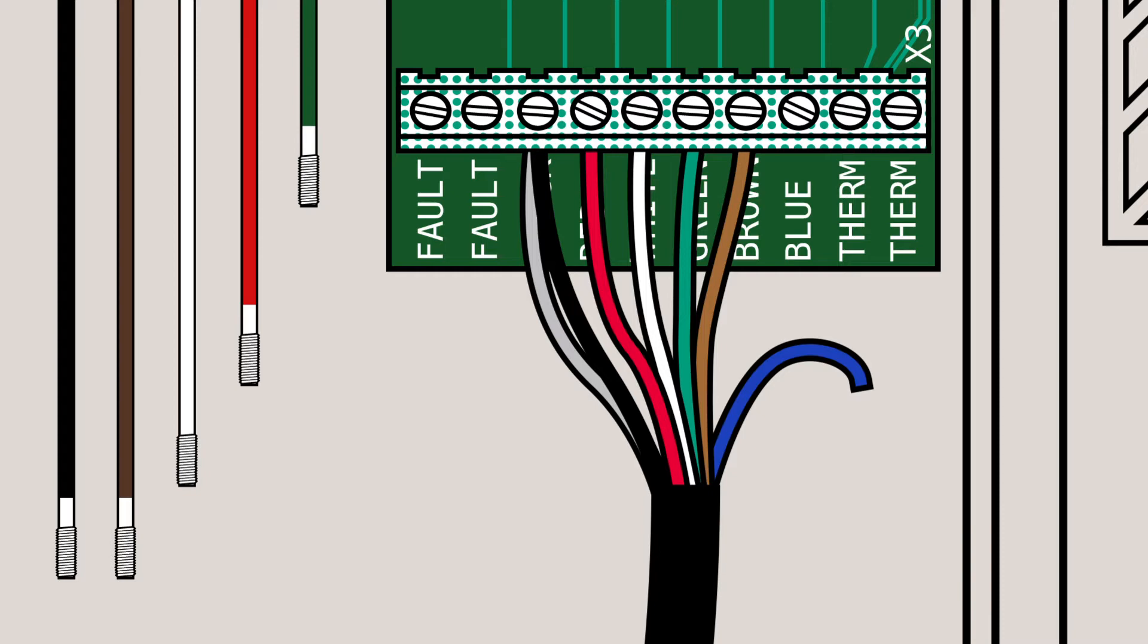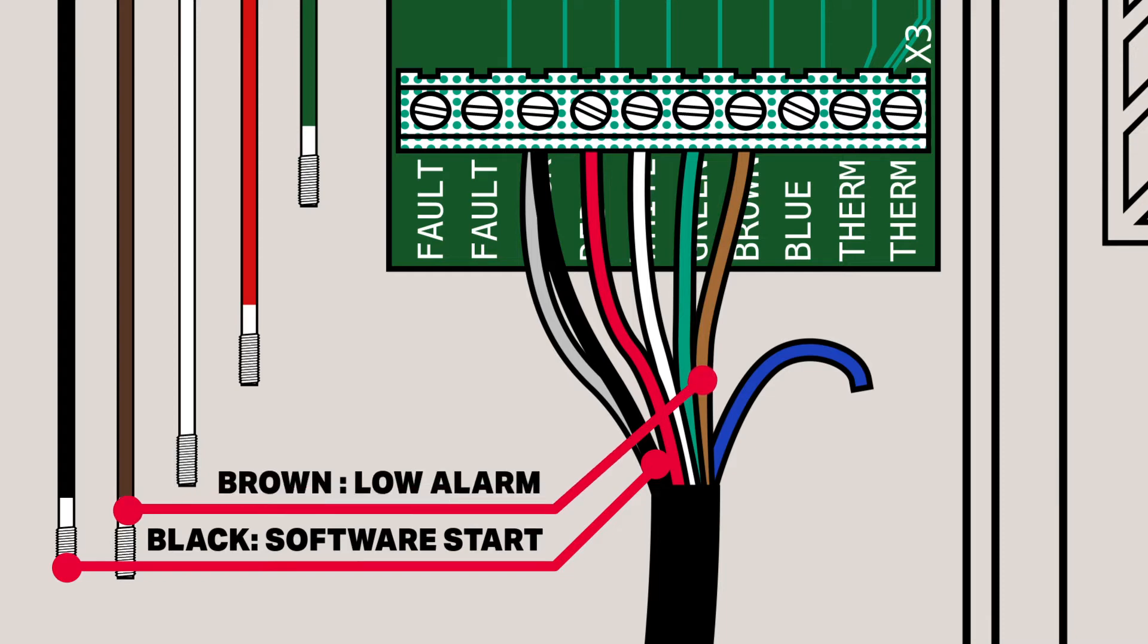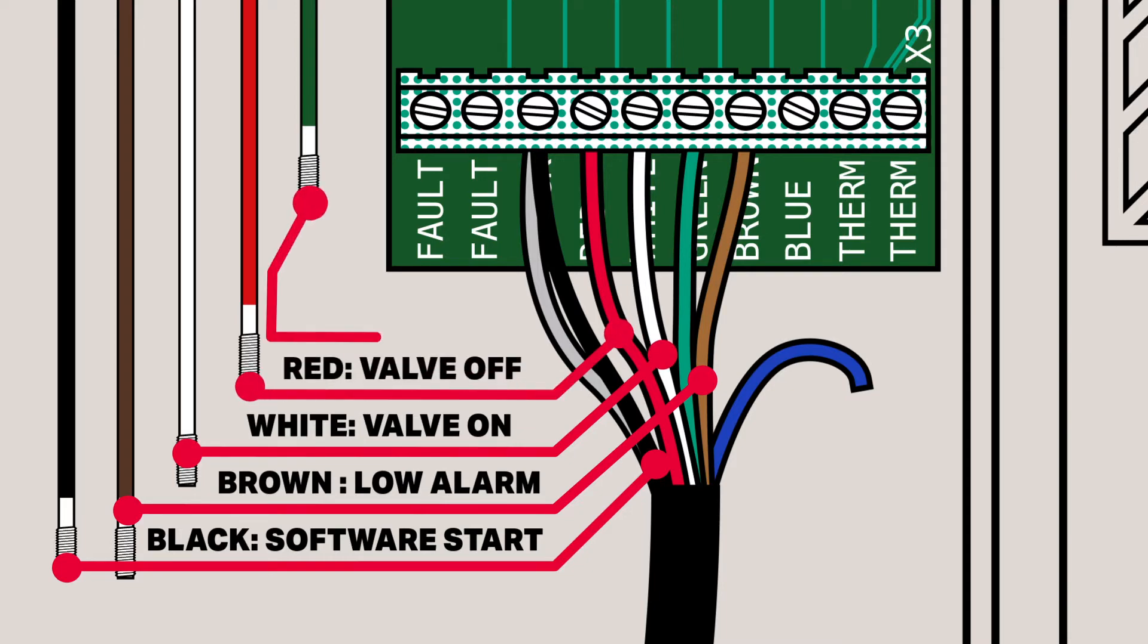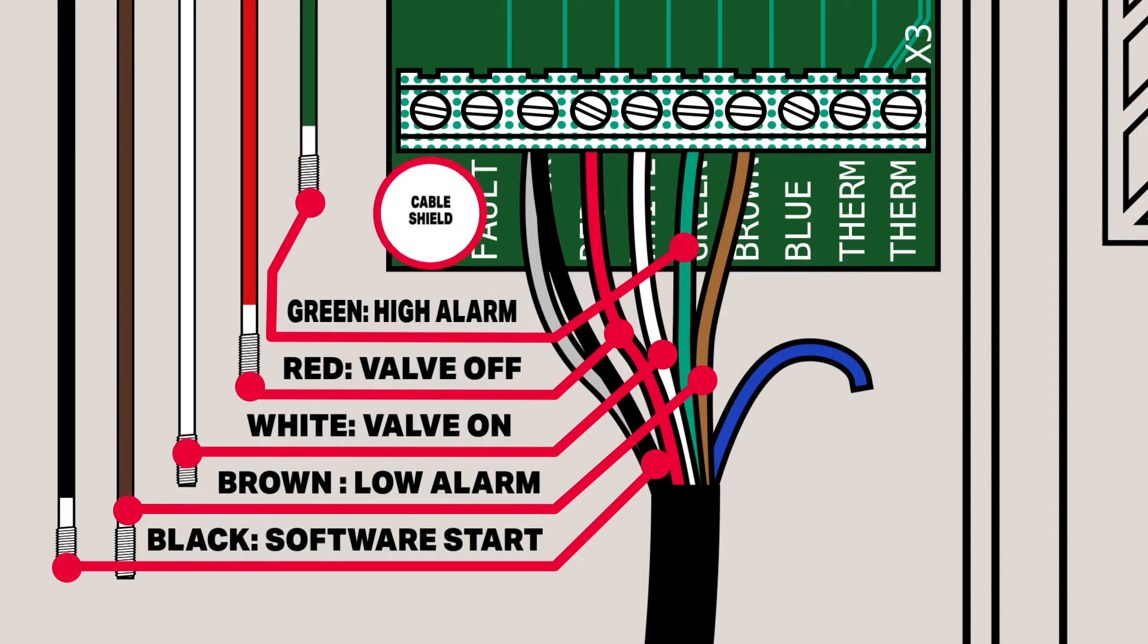From the longest rod to the shortest, the black is the software's start switch and needs to be as long or longer than the brown rod. The brown rod is the low alarm. The white turns the valve on, the red turns the valve off, and the green is the high alarm.